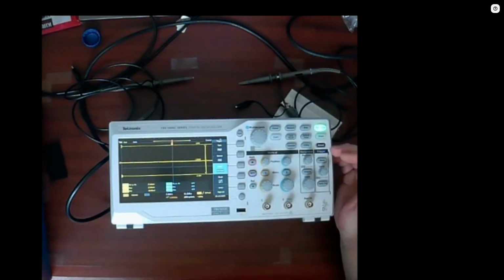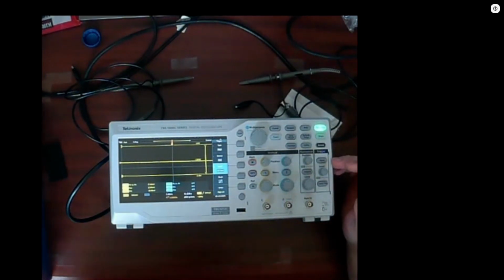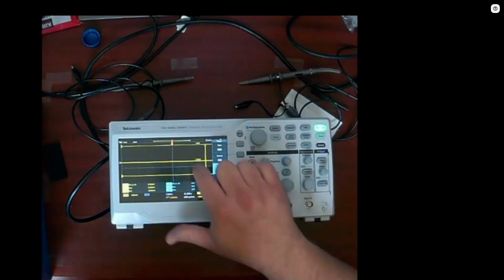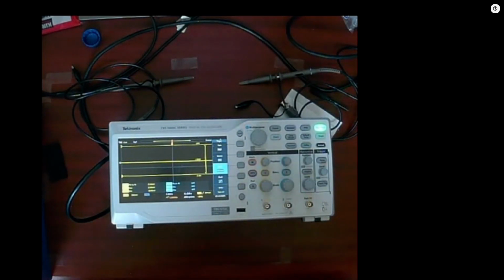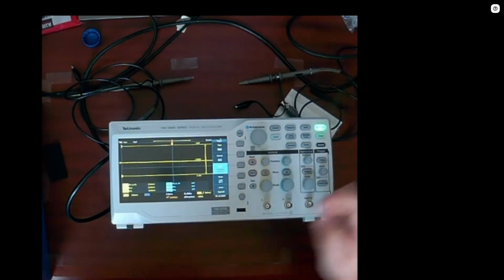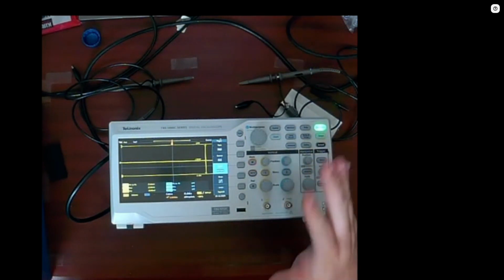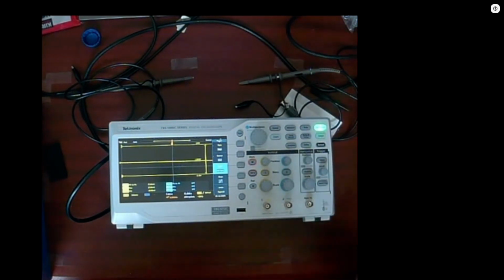A lot of times that's the other problem: my trigger is not set to where my waveform is. If I have a rolling waveform that's just running across and I can't get it to lock in, I need to adjust my trigger level. And I will show you how that works here in a little bit as well.